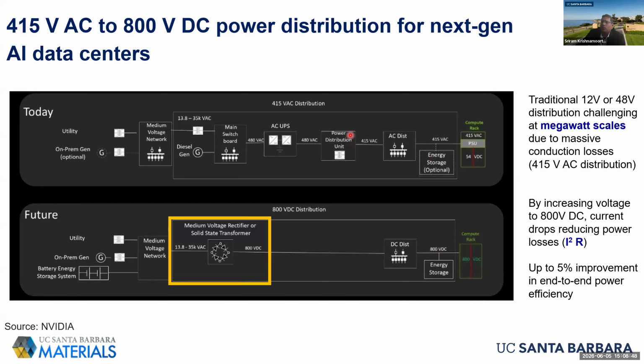By going from 415 volt AC to 800 volt DC, one can dramatically reduce the conduction losses. You reduce the current draw, which reduces the I squared R loss. In this estimate they worked out, that gives about a 5% improvement in end-to-end power efficiency, which is a big deal because 5% of a huge number is still a very huge number.